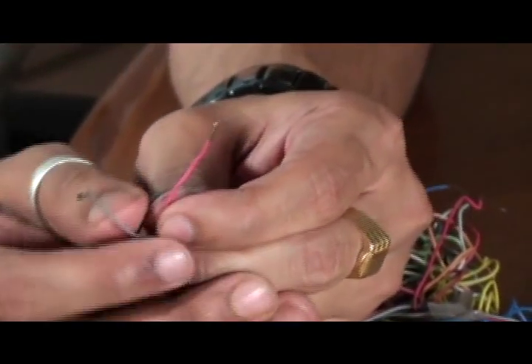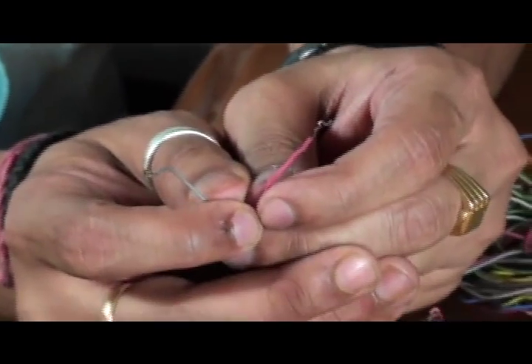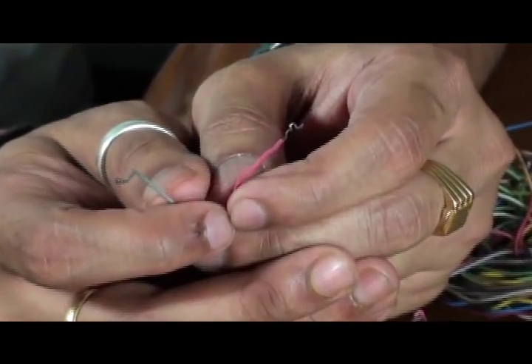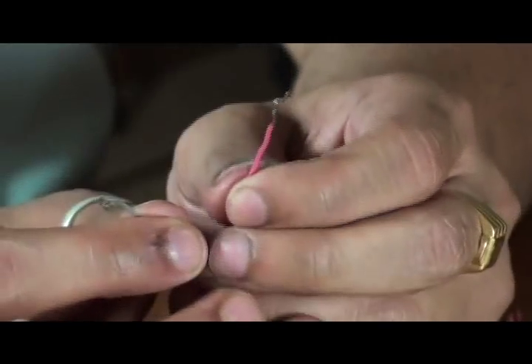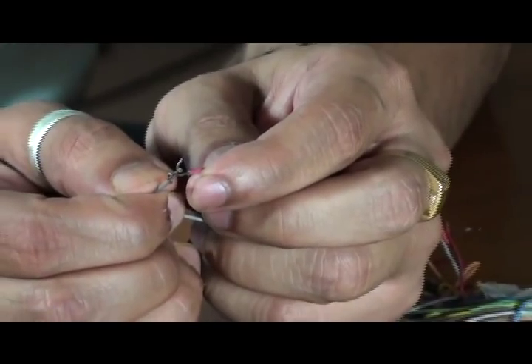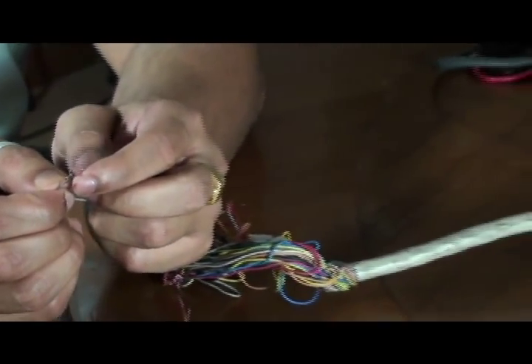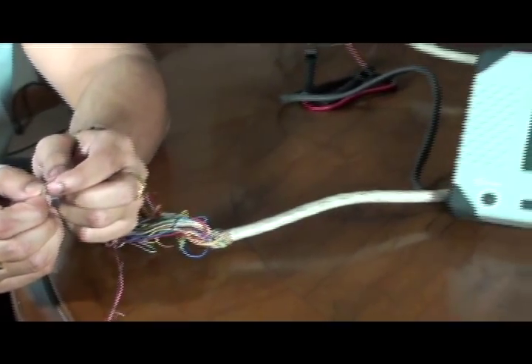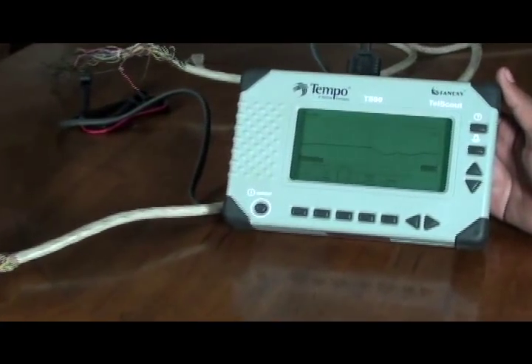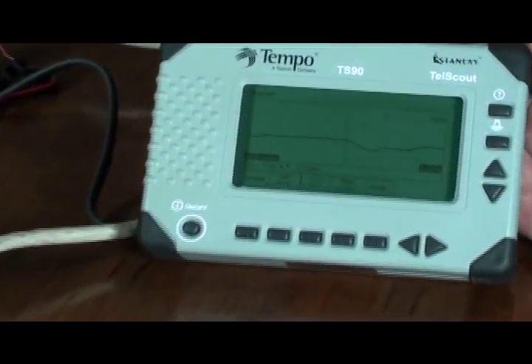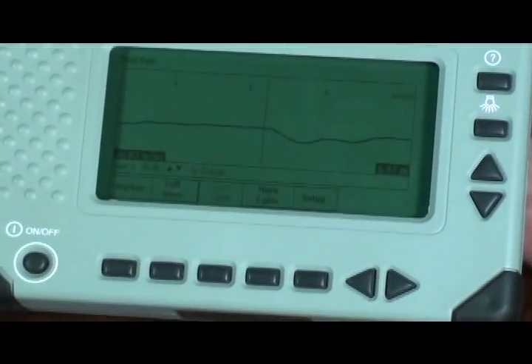To illustrate a short cable fault, we go to the other end of the cable and short the same pair. It suddenly shows a downward spurt in the graph, which means that the cable is short at a distance of 6.4 meters.